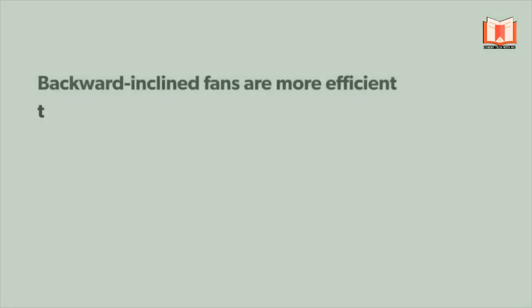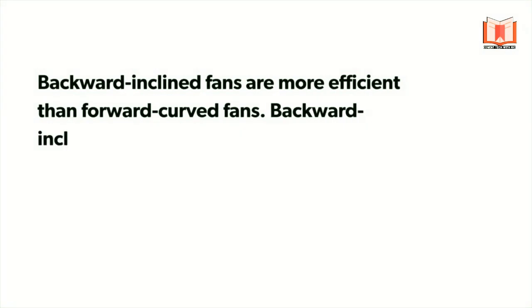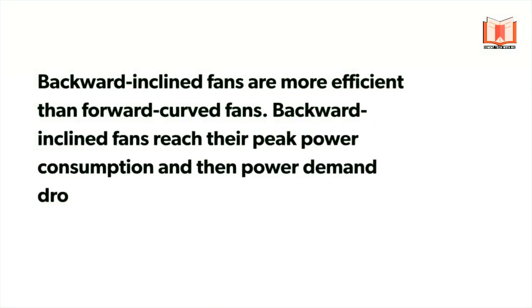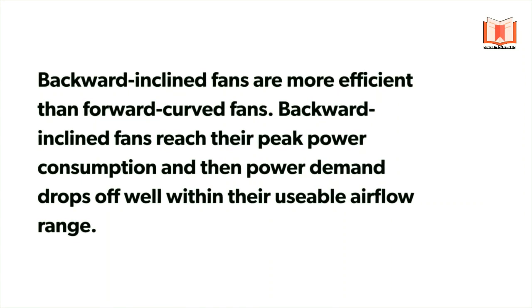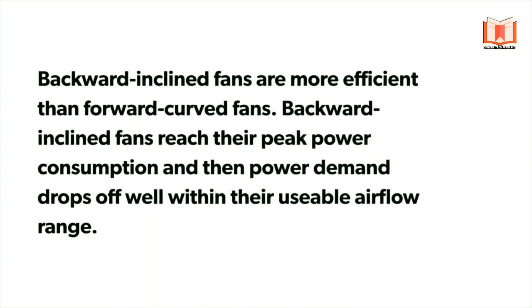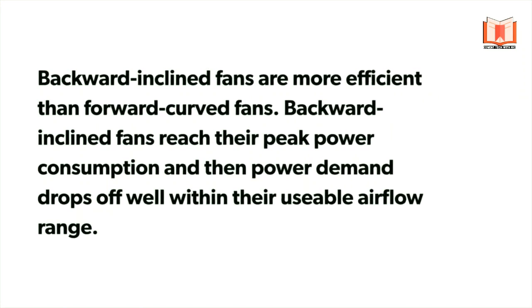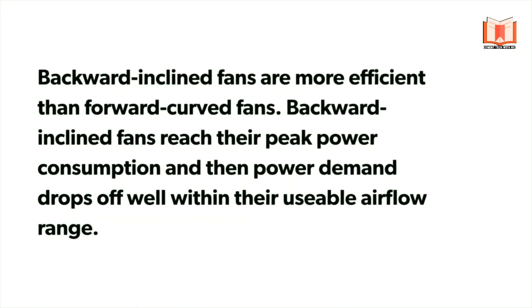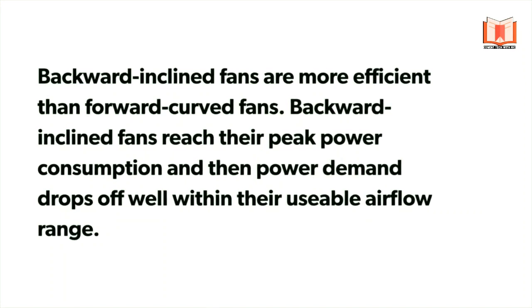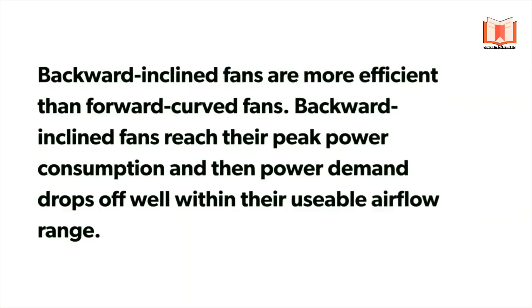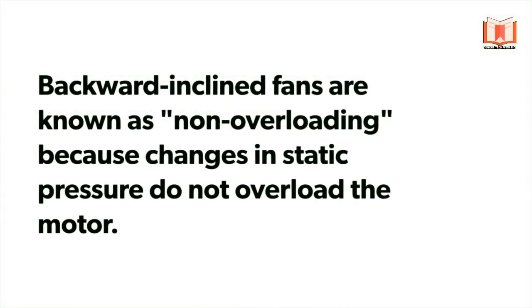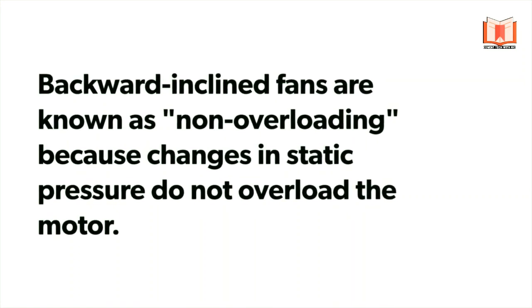Centrifugal flow fan types — Backward-curved fans: Backward-inclined fans are more efficient than forward-curve fans. Backward-inclined fans reach their peak power consumption, and power demand drops off well within their usable airflow range. Backward-inclined fans are known as non-overloading because changes in static pressure do not overload the motor.